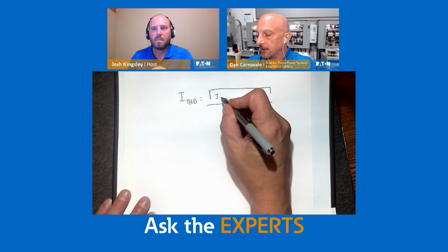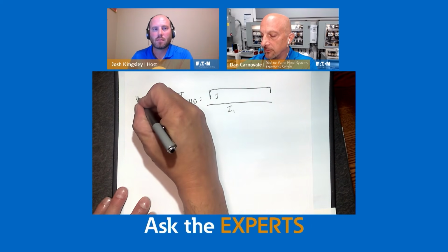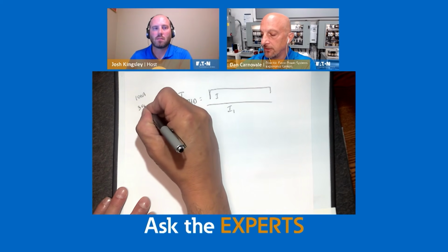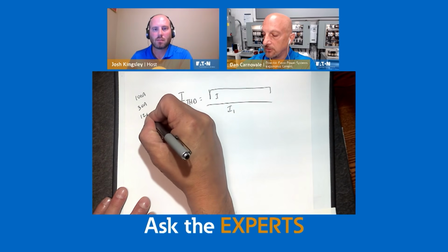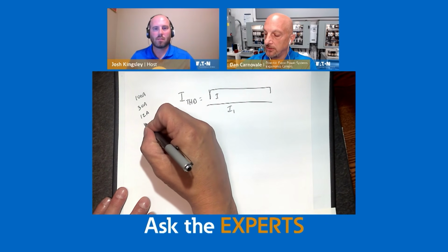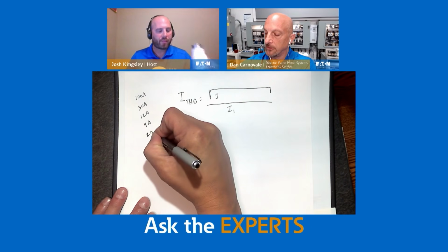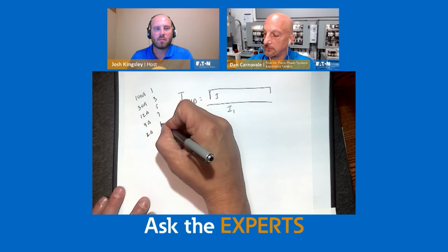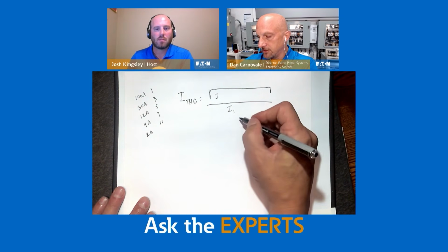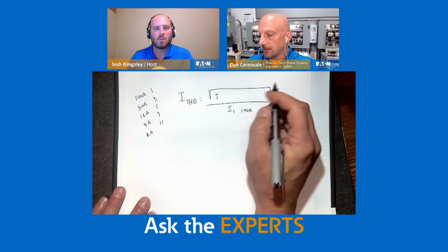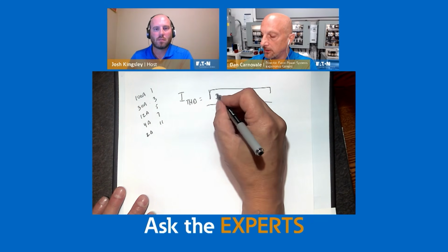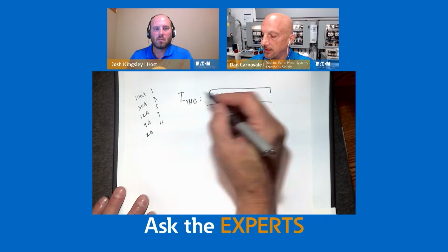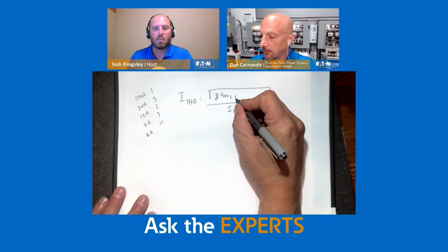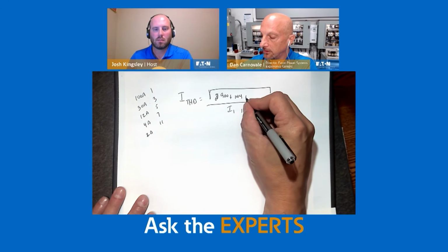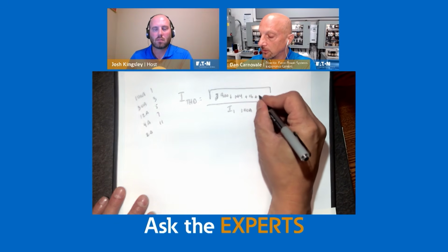So let's use an example where we have a fundamental of 100 amps, third harmonic 30 amps, fifth harmonic say 12 amps, seventh harmonic say 4 amps, and 11th harmonic 2 amps or whatever. The fundamental here is 100 amps. If I take 30 squared, I get 900, plus 12 squared, I get 144, 4 squared is 16, and 2 squared is 4.